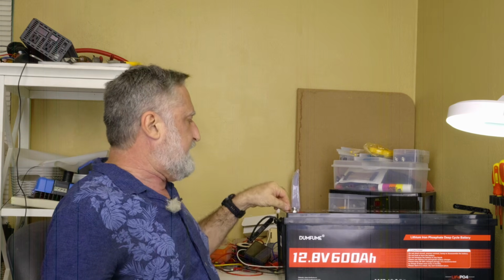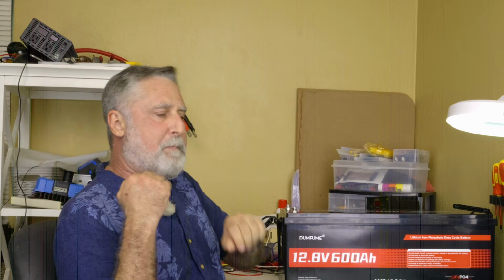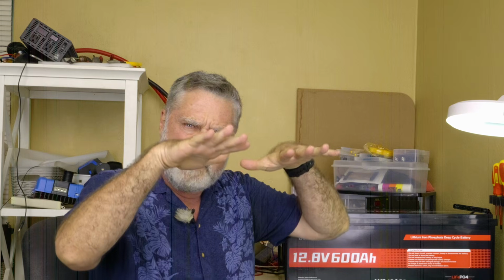So I contacted them, and they were nice enough to get a technical person in contact with me, and he gave me the numbers. They claim that the BMS, when it sees any cell above 3.525 volts, will apply the balancing load, which brings the capacity of that cell down. So the idea is, if you have a bunch of cells at different charge levels, the top ones will come down and meet the others.